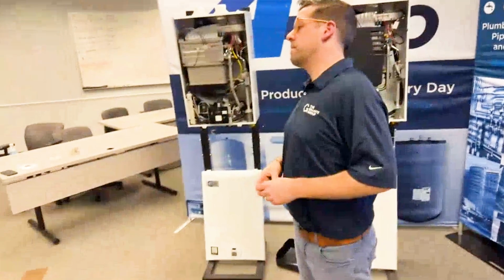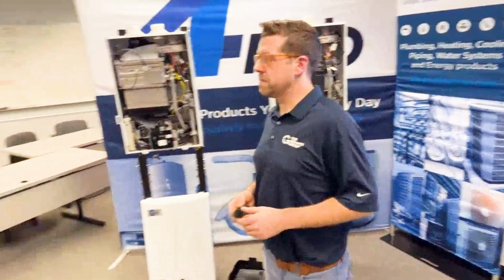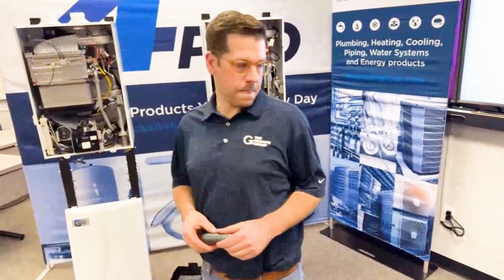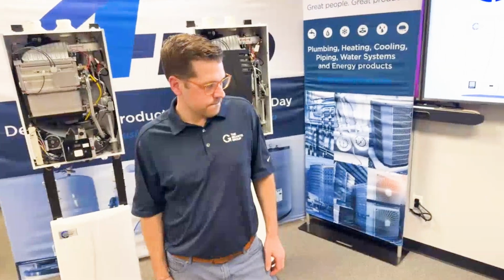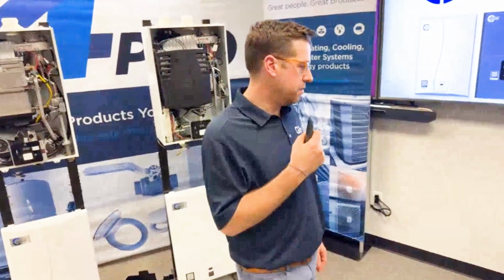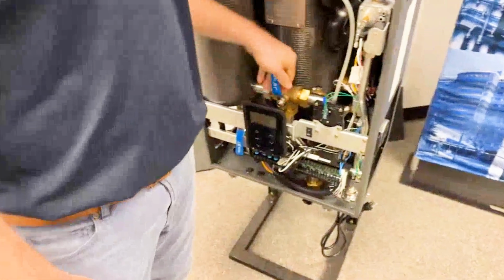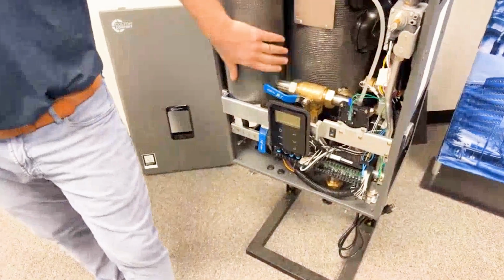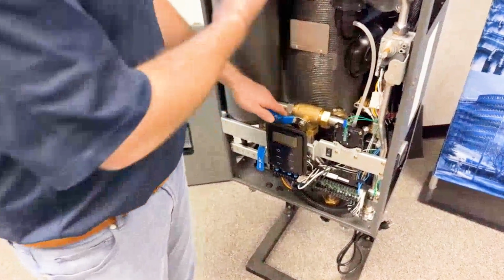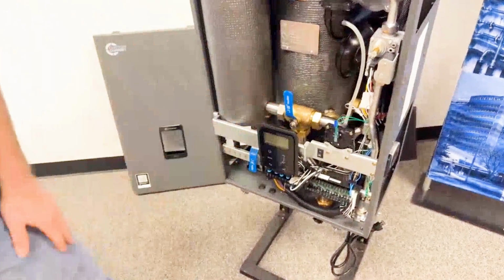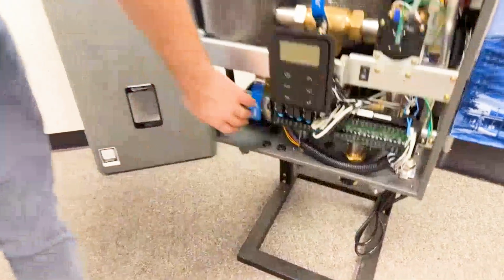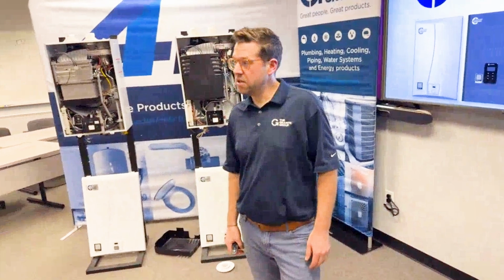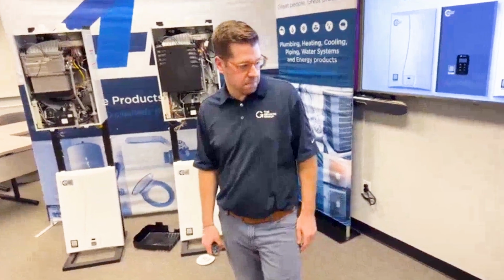This question is related, I believe, to the fire tube as well. It appears that inside the boiler cabinet there are two manual valves with blue handles. Can you explain their functions? The question was the blue handle ball valves inside the fire tube combi. These would be if you needed to isolate the buffer tank on this boiler. Let's say I have to replace the coil or the buffer tank here. You do have the ability to isolate it with these ball valves. You shouldn't need to touch them unless for some reason you need to isolate that buffer tank. So I would say, don't make an adjustment and get yourself in trouble. Out of the box, you should be good to go with the blue handle ball valves.